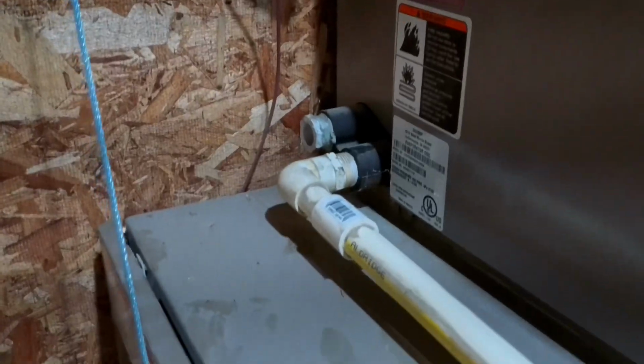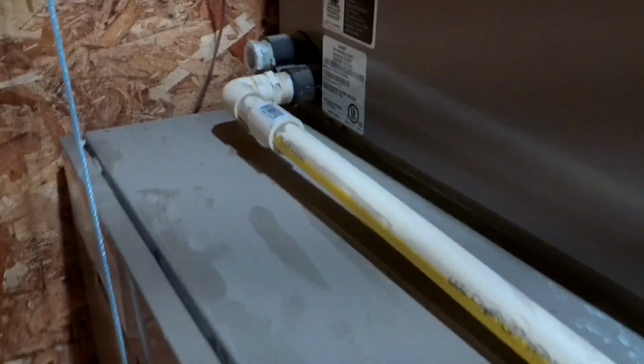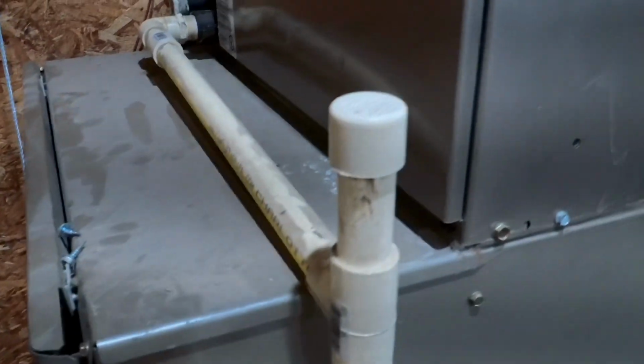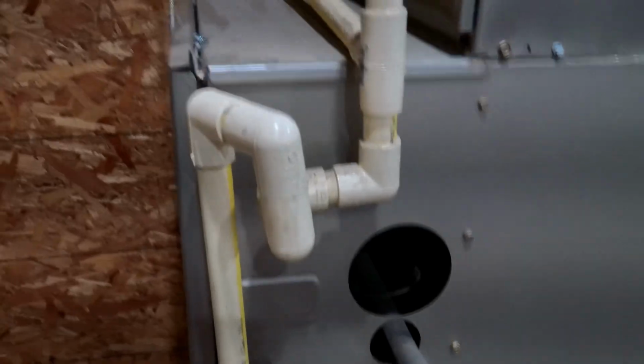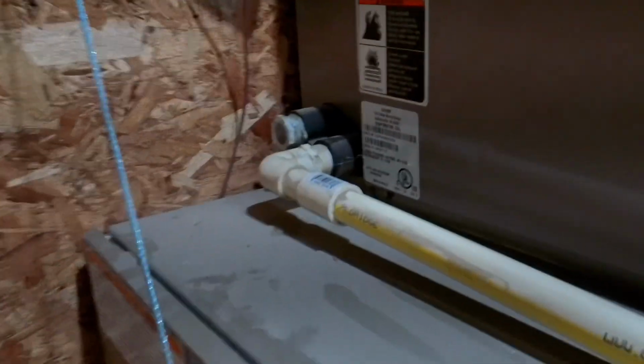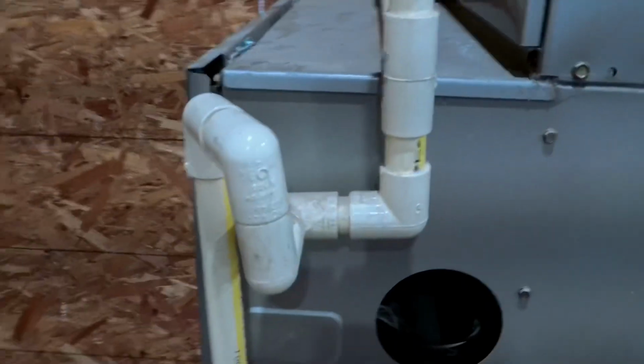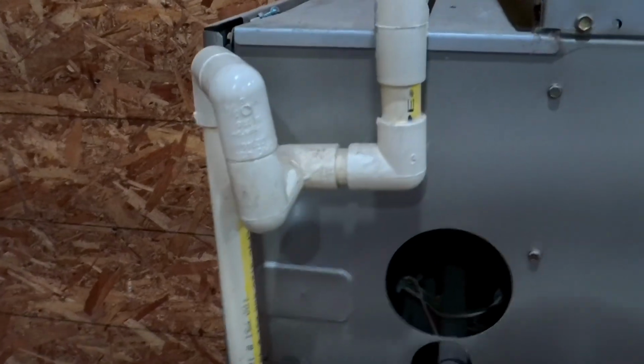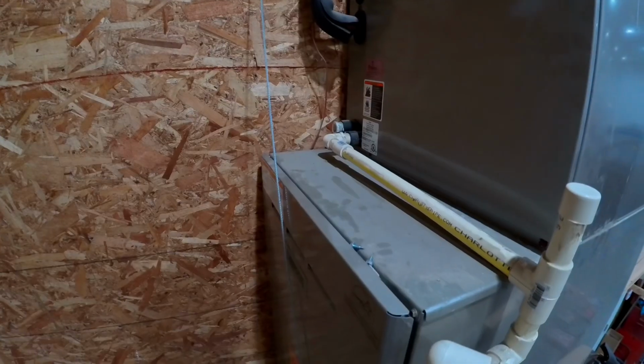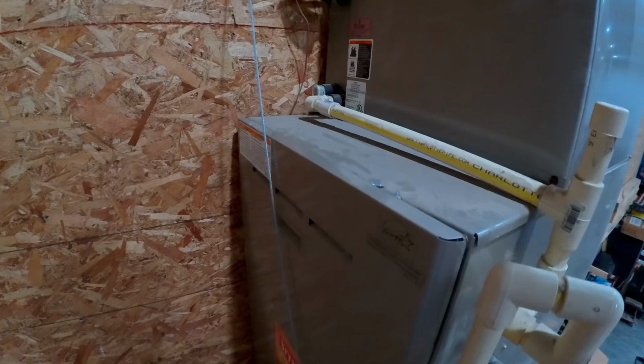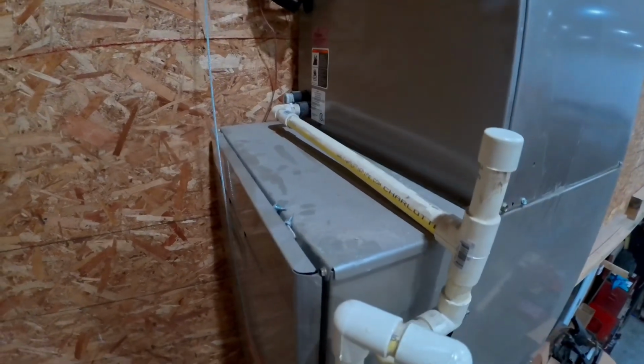All air conditioning systems are going to have a drain to drain the excess condensation away from the system. Most commonly, these will get plugged up either at the elbow coming straight out of the unit, or most common is in the P-trap area in this section right here. A plugged condensate is easy to repair, but usually requires opening the system up.